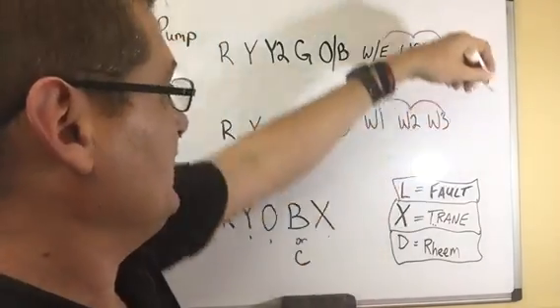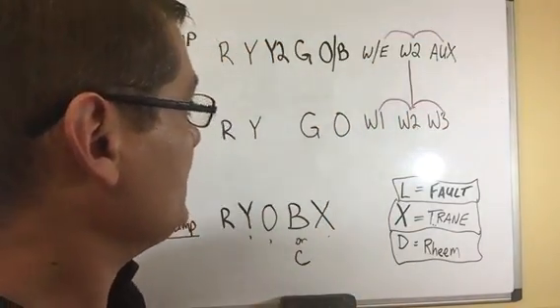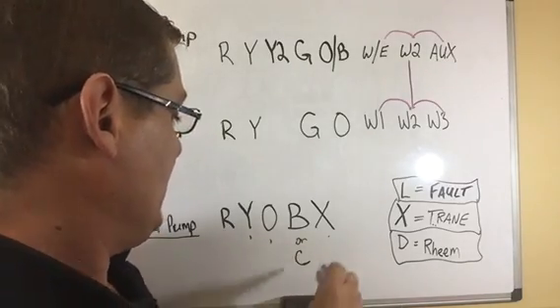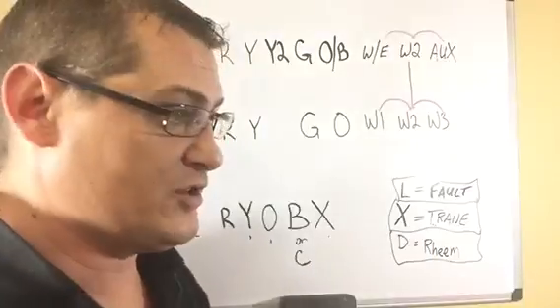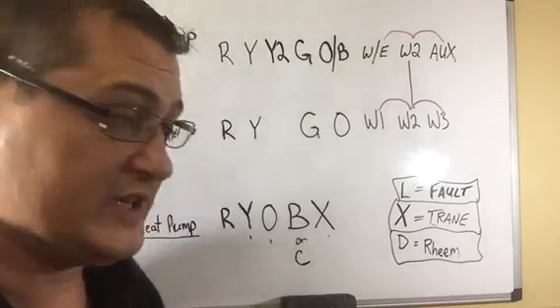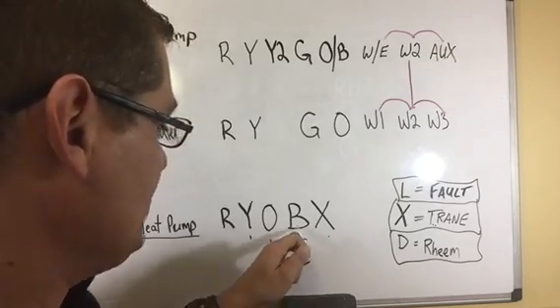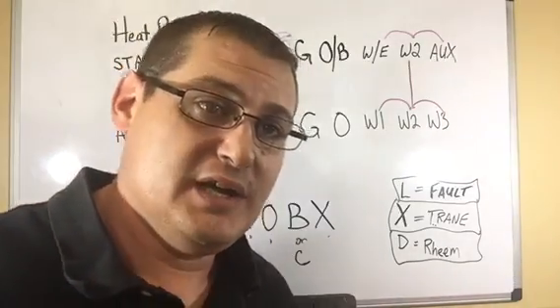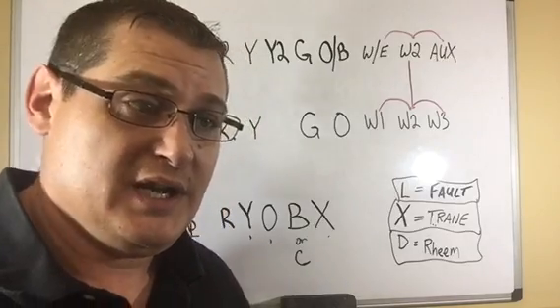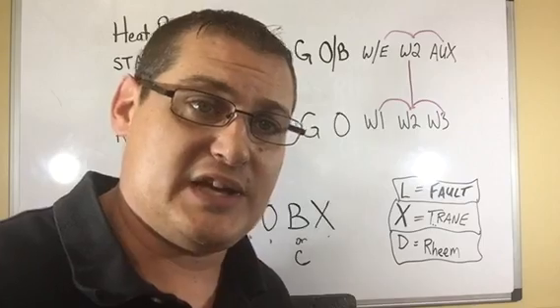This is a Trane example. Trane uses X to power up the strip heat whenever there's a call for defrost. One thing that Trane does that's a little bit different is they use B for their common, and they'll actually, I think they even use the blue wire for common. Like I said before, as long as you know what the terminal's doing, that's really all you need to know. Colors really don't matter. It just makes it easier.